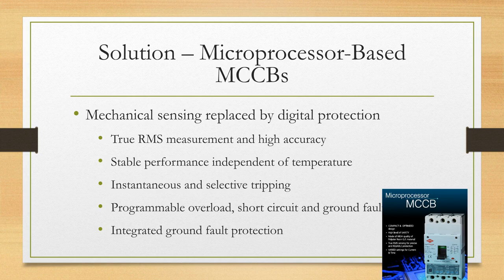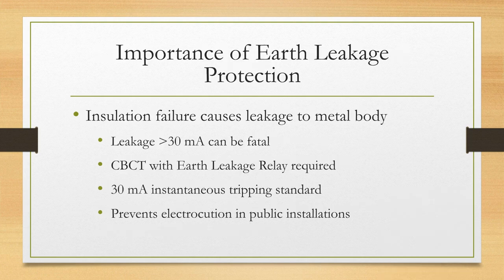These offer true RMS measurement, high accuracy, stable performance, and instantaneous selective tripping. They also provide programmable and integrated ground fault protection. Earth leakage protection is crucial because insulation failure can cause leakage to metal bodies. Leakage above 30 milliamperes can be fatal. A 30 milliamperes instantaneous tripping standard using a CBCT with an earth leakage relay prevents electrocution in public installations.